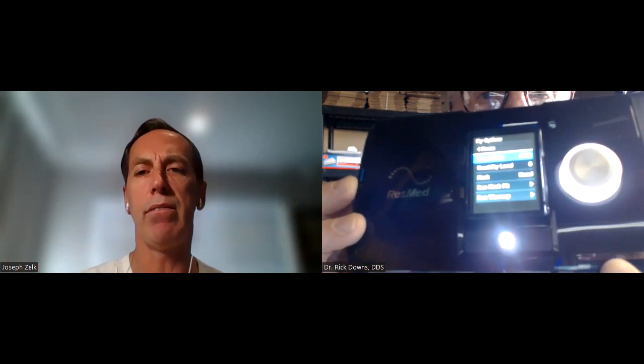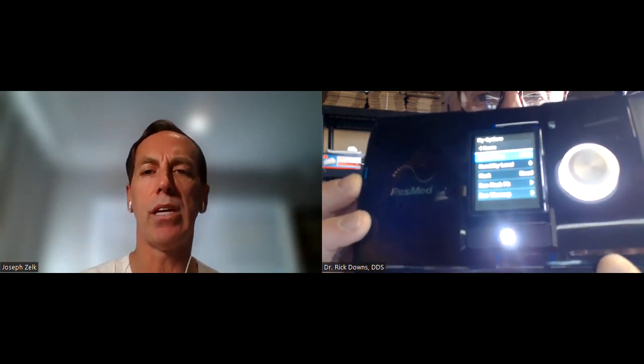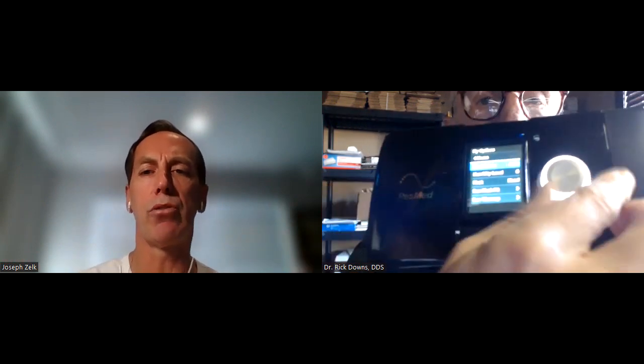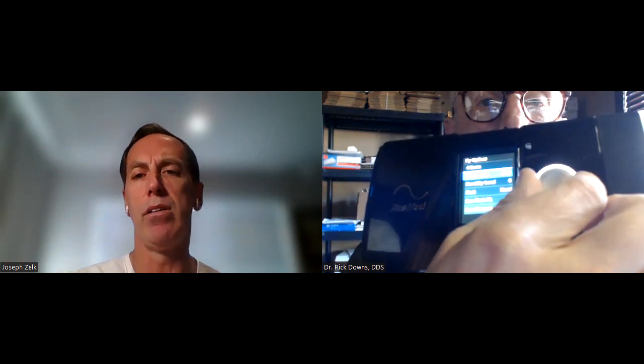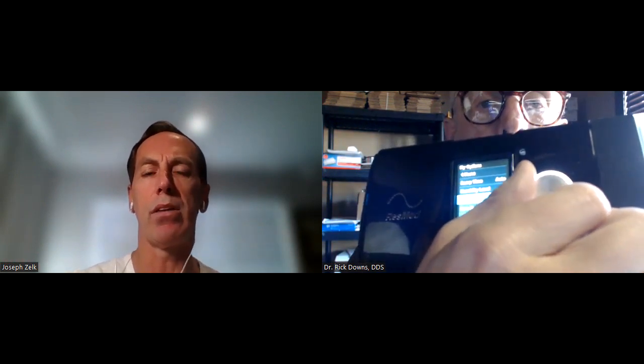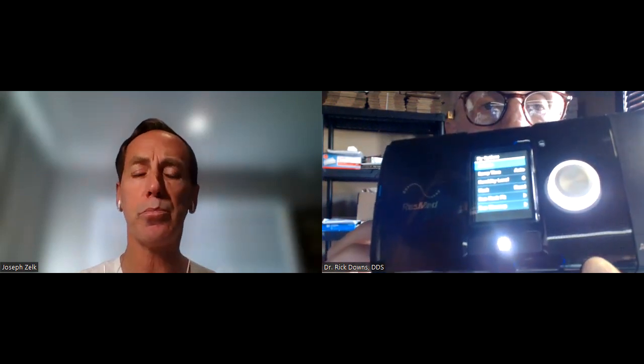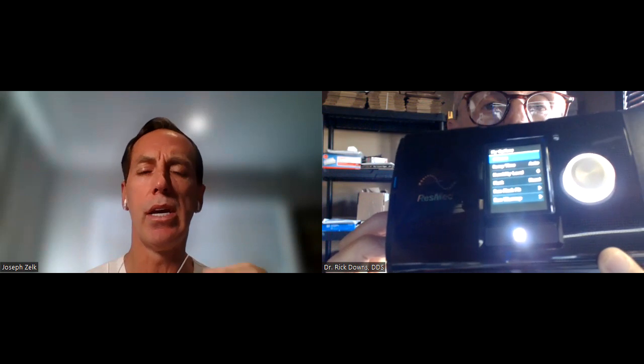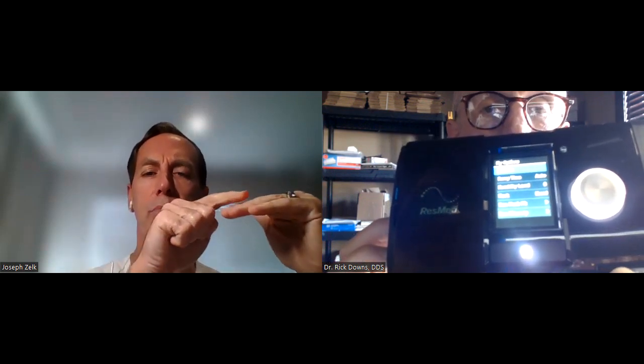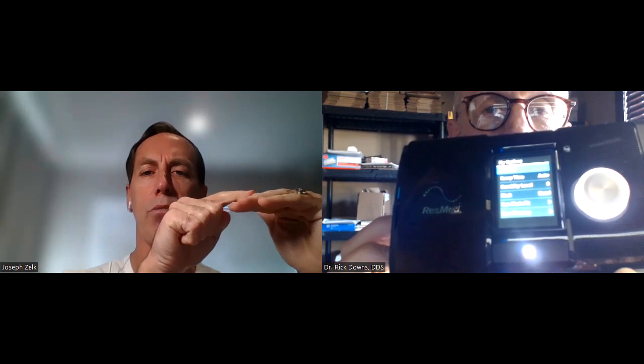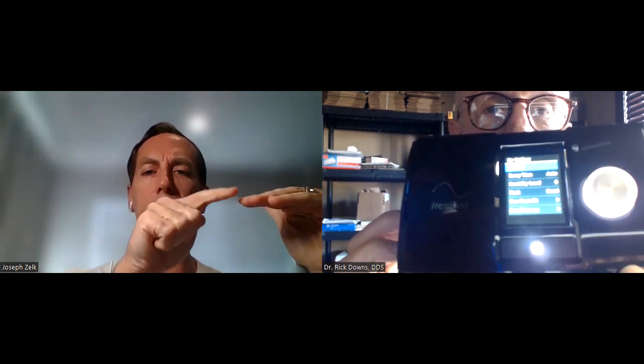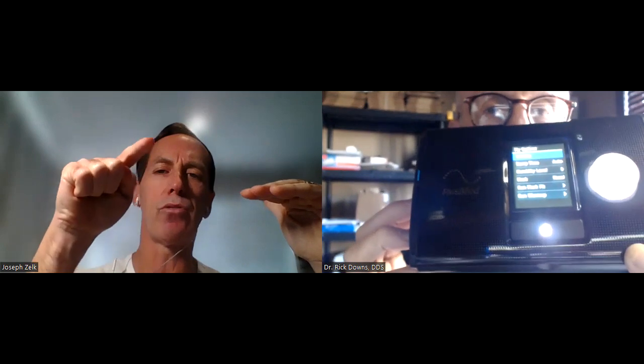So if it takes you 10, 15, 20 minutes to fall asleep, you'll typically set that ramp pressure at a low pressure of 5 for the 5, 10, 15, 20 minutes that it's going to take you to fall asleep. And then it'll start going into its range. So the way auto CPAP works is it looks at your average of every 3 breaths. So if you're falling asleep and you're in lighter sleep, you might need less pressure. So every 3 breaths, the pressure sensor will look at that pressure.